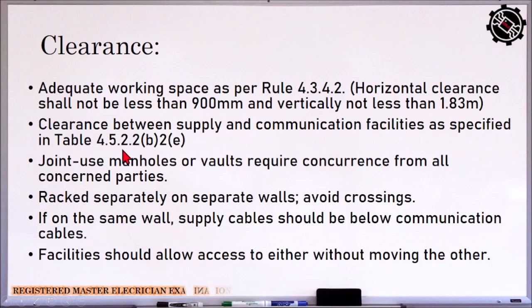If on the same wall, supply cable should be below communication cable. So if on the same wall, the supply cable should be below the communication cable. Now, for example, if this is our wall, and this is our communication cable, then below this will be our supply cable. And the clearance applicable here is the vertical clearance. So this will be 1.83 meters.